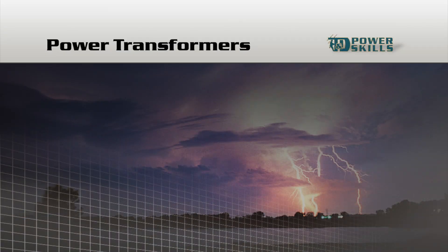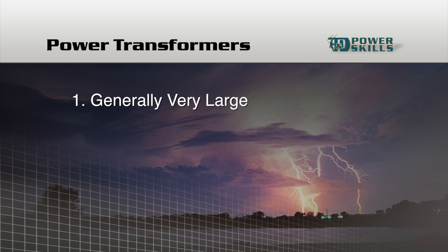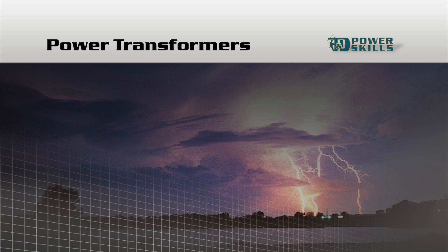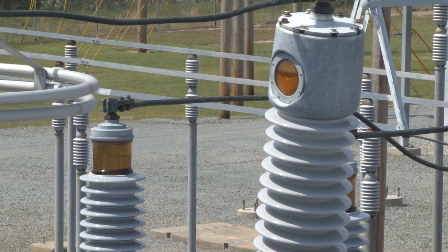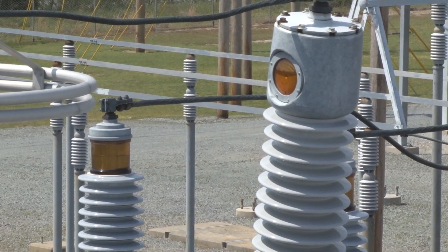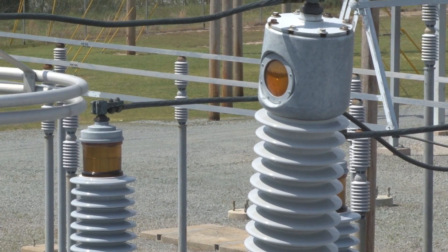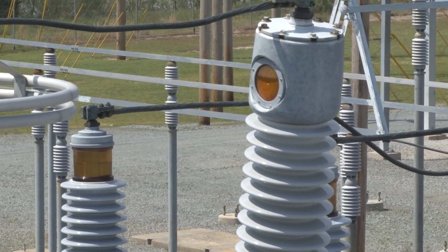A power transformer usually has at least two main recognizable features. It's generally large — larger than most other devices in a substation or switchyard — and it typically has bushings of at least two different sizes. A bushing is an insulating lining for a conductor that insulates the conductor as it passes through an enclosure, such as a transformer enclosure.